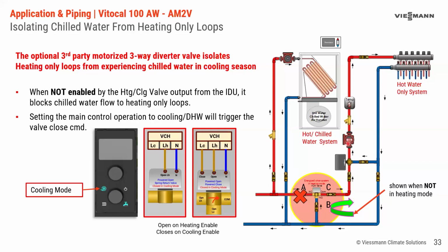So if this pump is running, and like I said, you can use a two-way or three-way valve. I prefer the three-way valves because if I use a two-way valve and this pump is running at some point in the summertime, even somebody testing it or running it, or it's plugged into the wall, whatever the scenarios where this pump might run in the summertime, if I don't have a three-way valve, this pump is going to pump into a dead head, and that's going to be detrimental to the life of the pump.